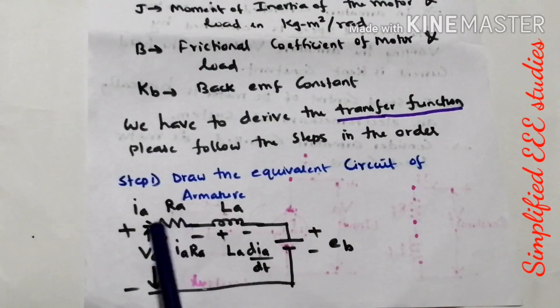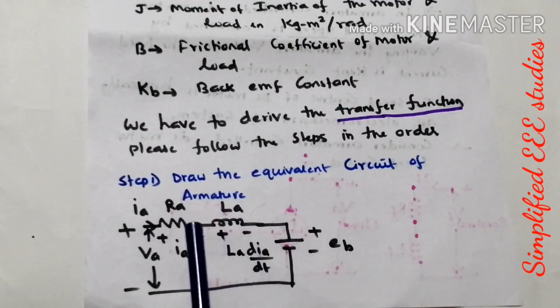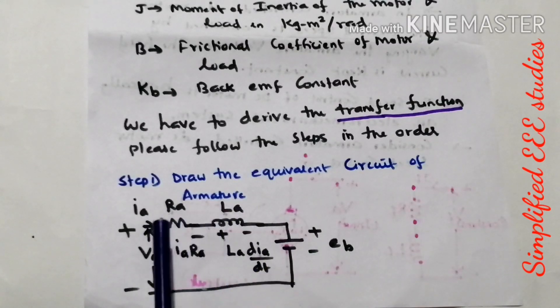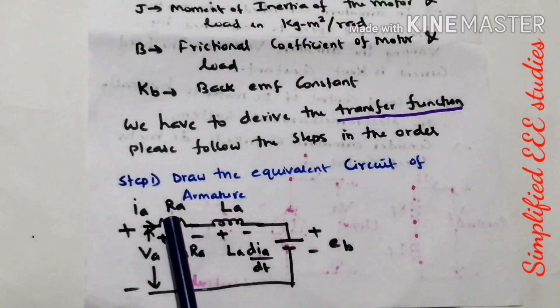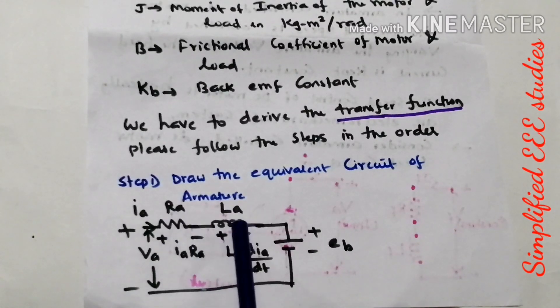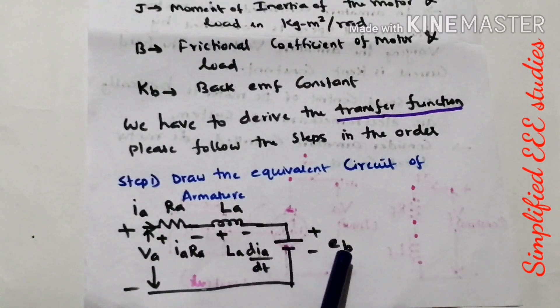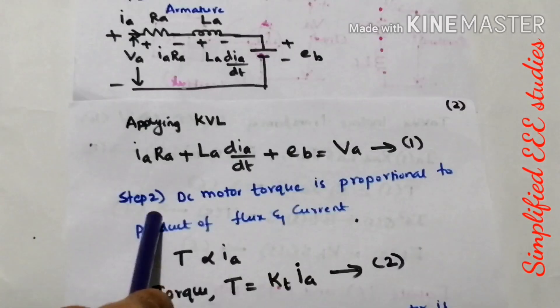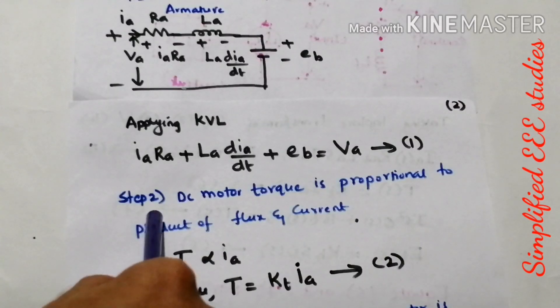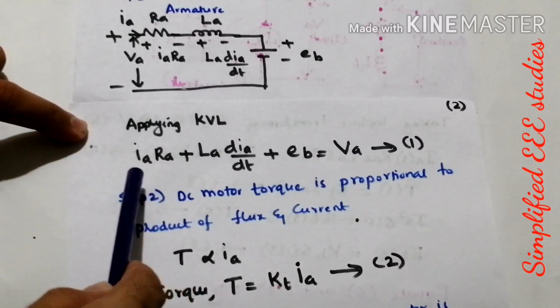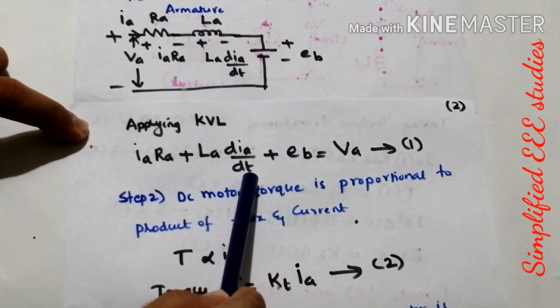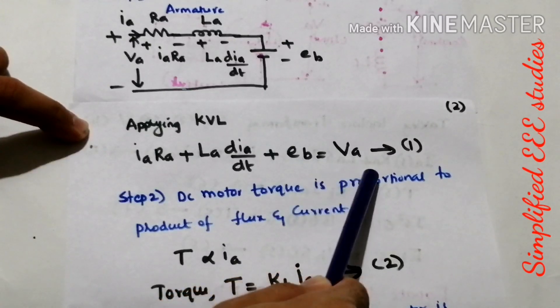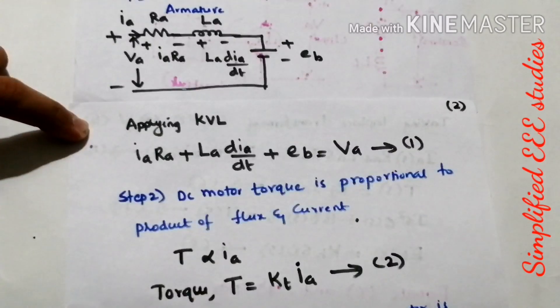First and foremost, you need to draw the equivalent circuit of the armature. As you can see, this is the equivalent circuit of armature. You have to represent armature resistance Ra, then armature inductance La, the back EMF, and the supply voltage Va. Now you have to apply KVL. By looking at the diagram, you can directly apply KVL, and you will get: Ia·Ra + La·(dIa/dt) + Eb = Va. Please call this equation number 1.